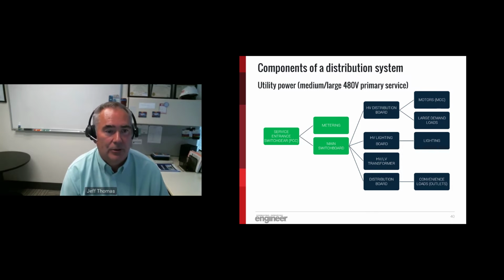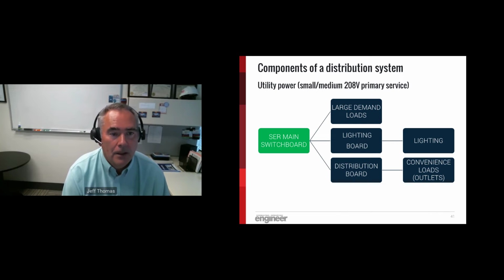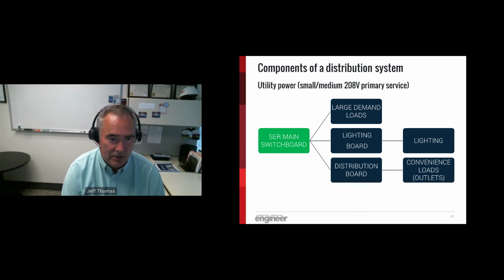All right, this is pretty typical for a larger installation. What about smaller installations? Suppose we're doing a bank or a convenience store. We don't need 480 volt service. We don't have huge motors or huge demand. So again, we'd have our service entrance rated switchboard. And if we had air conditioners, maybe they're 208 volt three phase, we can connect those directly. We could have a lighting board. Nowadays with LED lighting, we can run 120 volt lighting circuits if we're not going very far, or we can run 208 volt lighting circuits. And then since our main service is 208 volt three phase, we can have a distribution board and break that out and get 120 volts line to neutral with no transformer. So this is a simpler installation, but again, a much smaller installation.